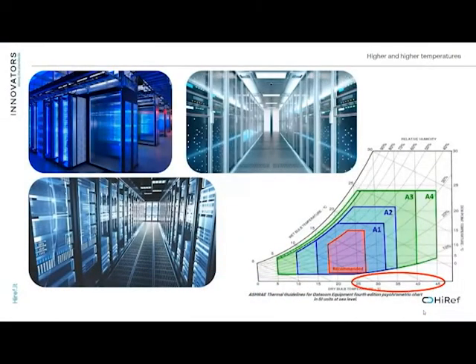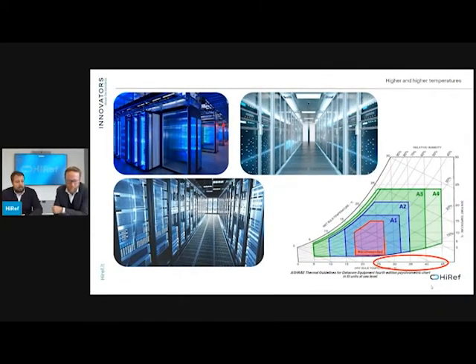Yes, there are some technical aspects we have to consider. For sure, we have to think about modern data centers where there's a containment system able to separate the cold side from the hot side. This gives the possibility to increase the temperature outside from the devices, coming to the cooling devices, combined with the higher temperature that the ASHRAE recommendation allows for supplying the servers.